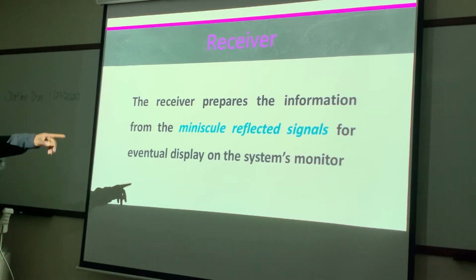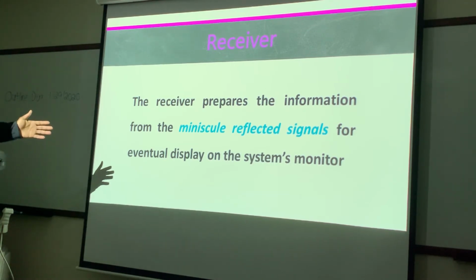So the receiver prepares the information from those minuscule reflected signals for eventual display on our monitor. So it's basically going to process our reflected sound beam, or our reflected electrical signals, right? Because our sound beams are going to vibrate the PZT. The PZT is going to effectively use the piezoelectric effect and turn those sound waves into electrical signals. Those electrical signals are going to be received by the beamformer. That beamformer is effectively going to send those to the receiver, basically, like I said, for preparation or processing for display, so we can see what we're doing.